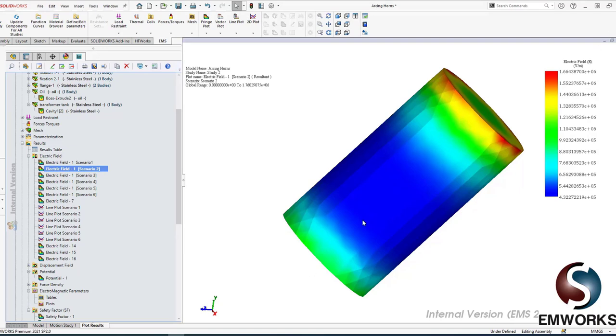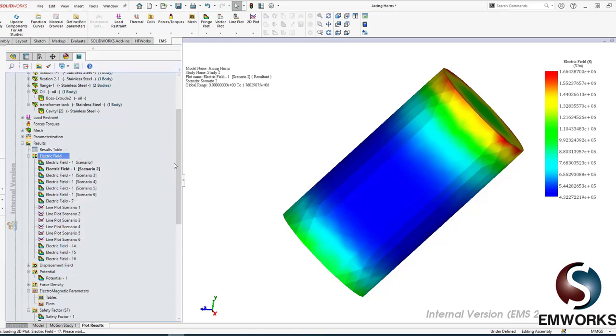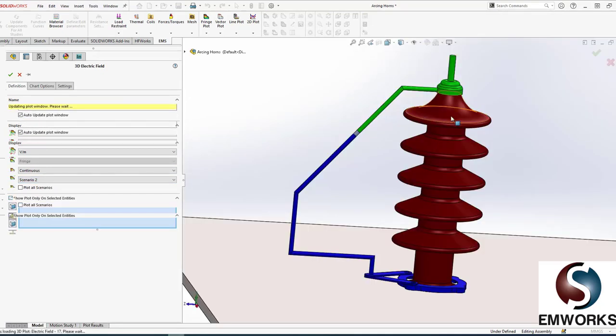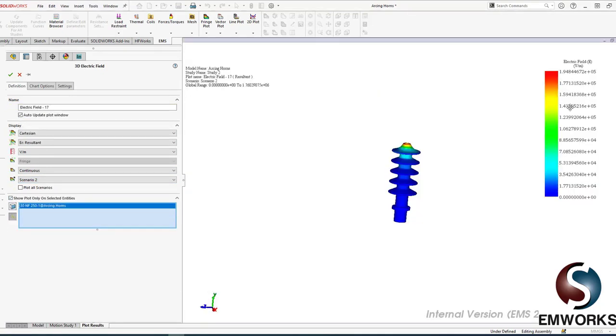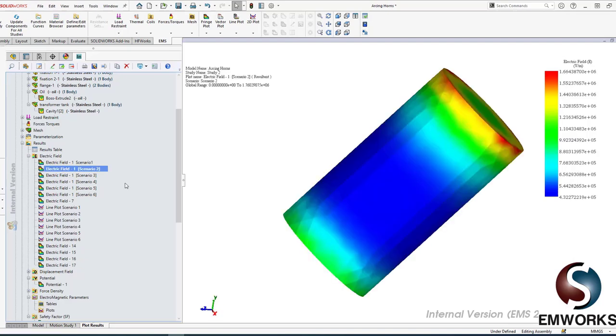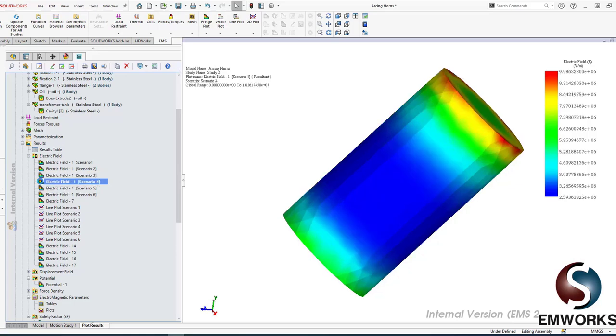If I look at the electric field in the insulator for scenario two and say show plots only in the insulator, it's nice. It is much below the breakdown, so there's no breakdown in the insulator and there's no breakdown in the air. So it is the proper size of the air gap. If it was much smaller, it could generate corona, which is undesirable at that voltage. Now let's look at scenario three. I'm still at 10,000 volts. Even at 10, 12.5, 15 millimeters, I'm fine. There's no breakdown. The voltage is much below 3 times 10 to the power of 6, so I'm fine. There's no breakdown.